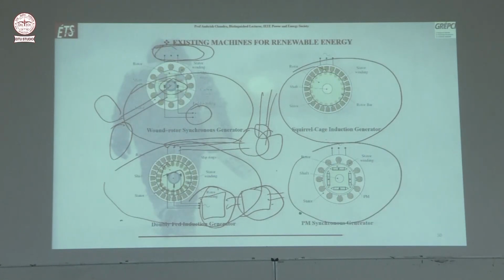And then PMSG, like yesterday we discussed, you have permanent magnets here, and then because with the variable wind, the frequency will change here, so you need two full size back-to-back converter. So if this machine is of 5 megawatt capacity, you need 5 megawatt capacity this converter and 5 megawatt this converter, so it will increase the cost. And on top of that, you have permanent magnet, which may increase the cost of the machine. So overall cost of the machine is increased. So this is what actually, it depends how much money you have, how many machines you have bought, how you can negotiate with the company which is providing PMSGs and those things. So this all depends on that.